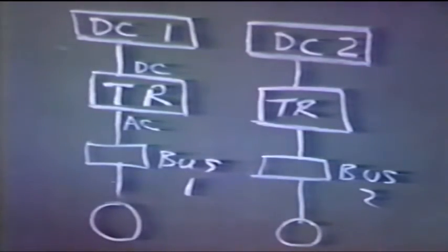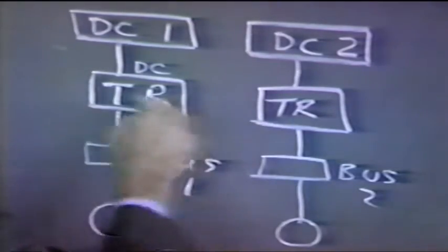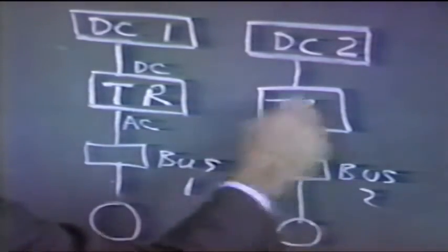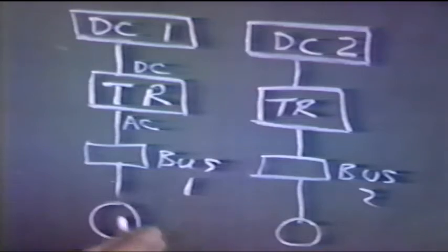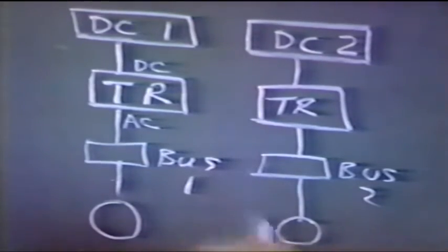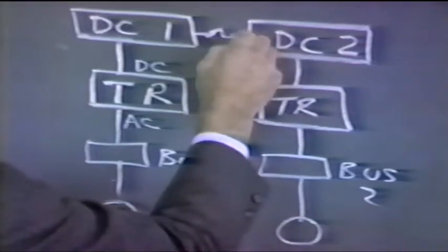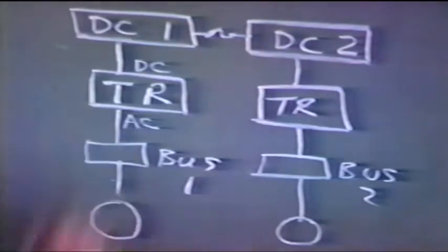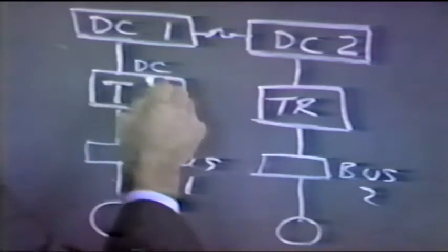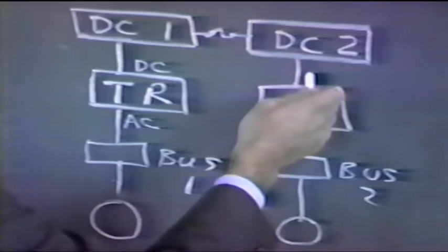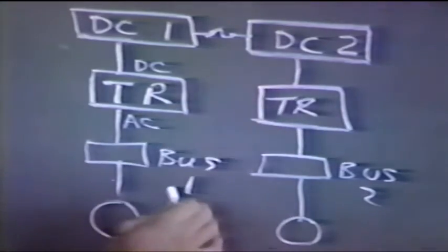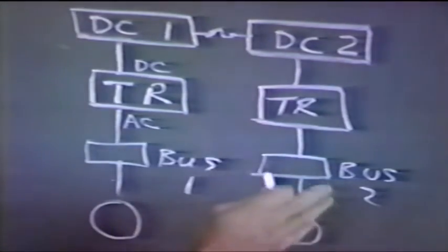Either one of these TRs, either one of these buses powering the TRs, can handle the entire DC load. How does it do that? Well, these two buses are tied together through a current limiter device. I call it a fuse. It might be placed in some arrangement down below the bus so that we could isolate the transformer rectifiers, but we're talking in general terms now.